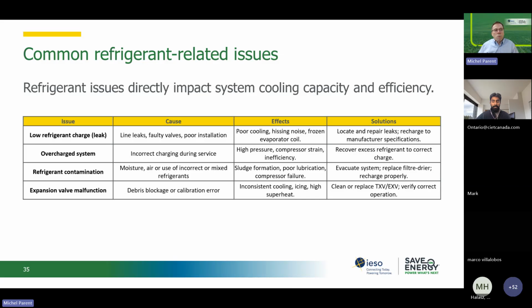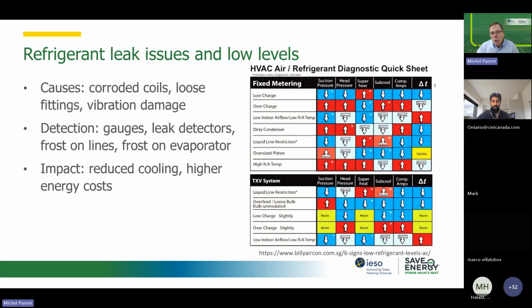Can you come over? Those are really issues to help you know what's going on with your system, knowing that you're unlikely to fix that without a third-party contractor coming in to do the work, unless your team has the proper expertise in refrigeration systems. So again, a little table that will help you do diagnostics on your refrigerant if you've got a fixed metering system, which is not that common in commercial buildings. You usually will have more of an active system. The fixed metering system is a capillary tube, where most of our DX systems will have a TXV or electronic metering valve. So this table would be more appropriate for most of your systems.